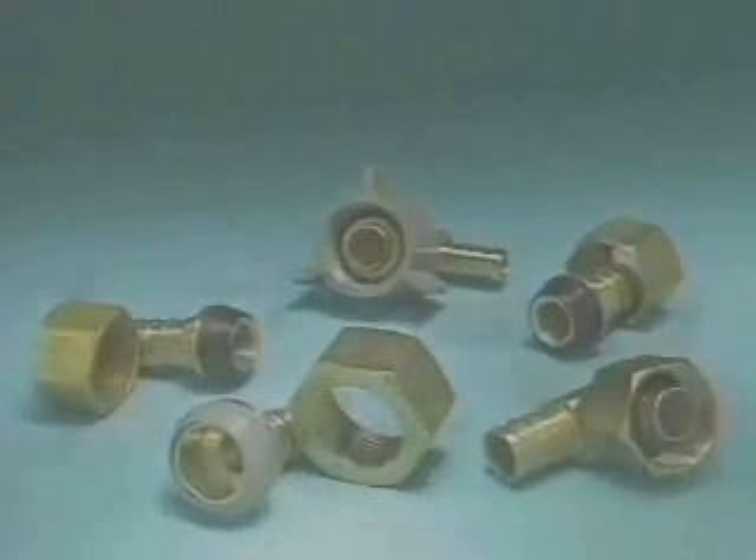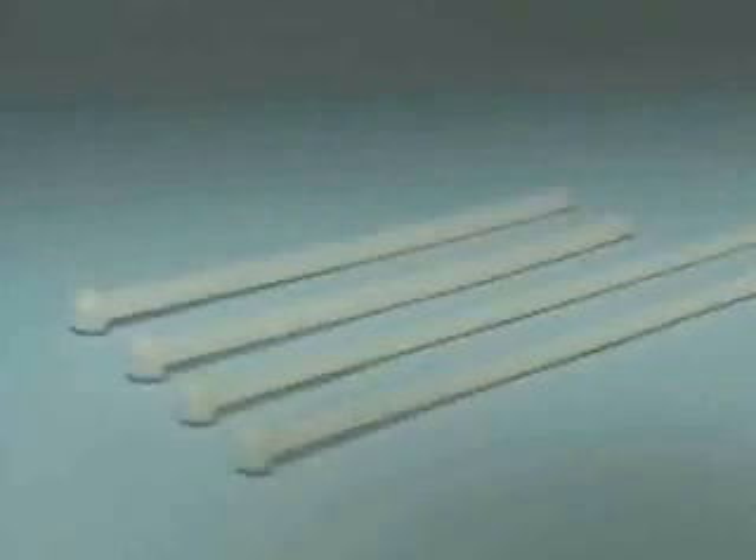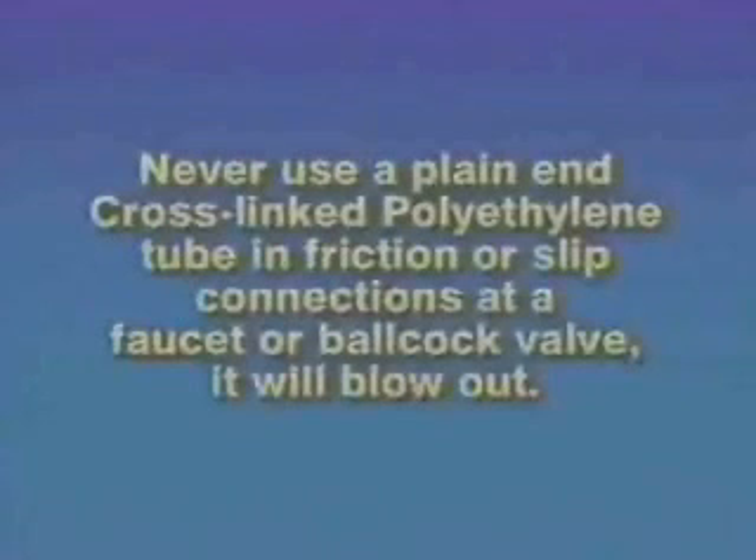Zurn has a full line of either plastic or brass supply stops with a variety of inlet and outlet configurations. Zurn also has a line of cross-linked polyethylene supply tubes. These tubes come with cones formed on the end of the tube for a permanent connection. Cones suitable for faucets or ball caulk valves are available, and the tubes come in a variety of lengths. Never use a plain end cross-linked polyethylene tube in friction or slip connections at a faucet or ballcock valve because it will blow out.